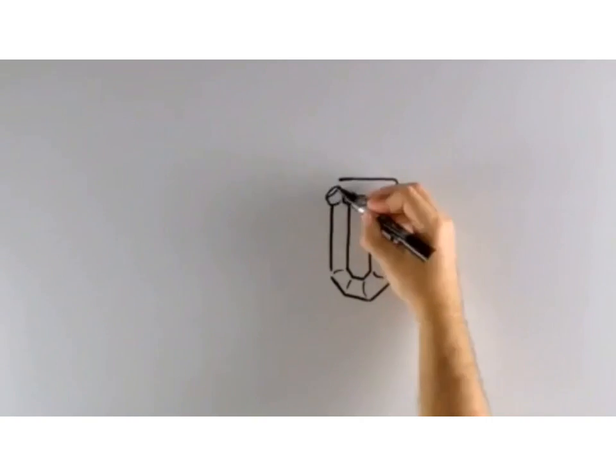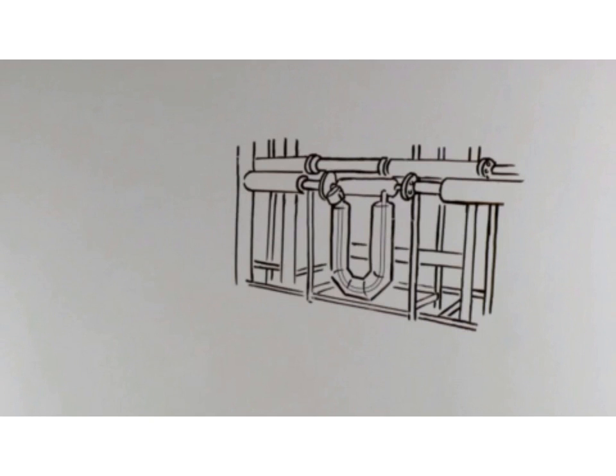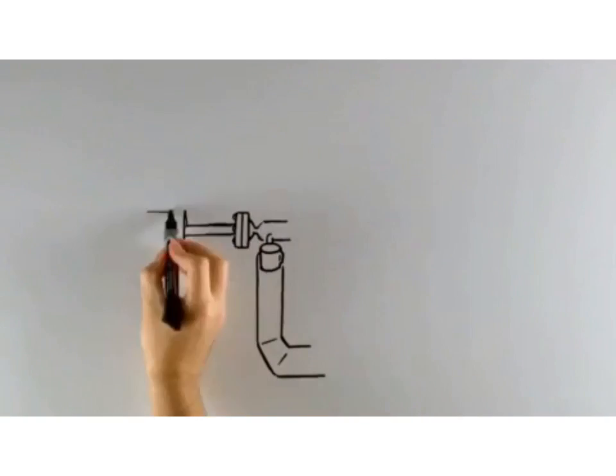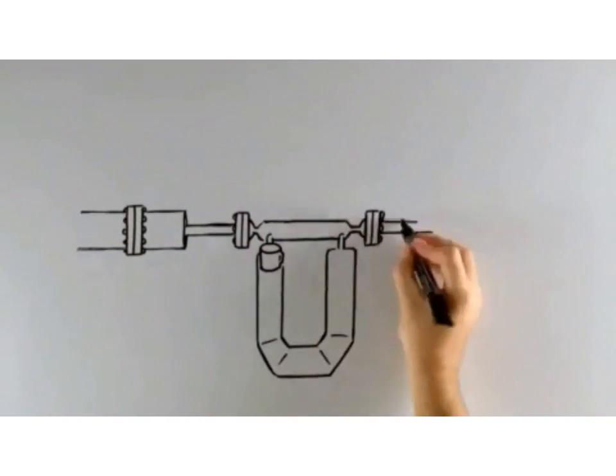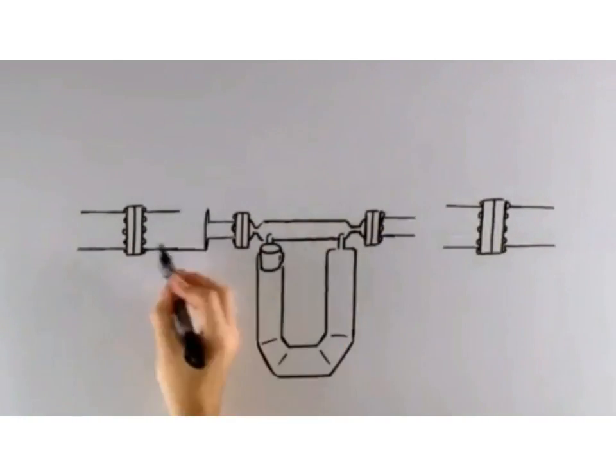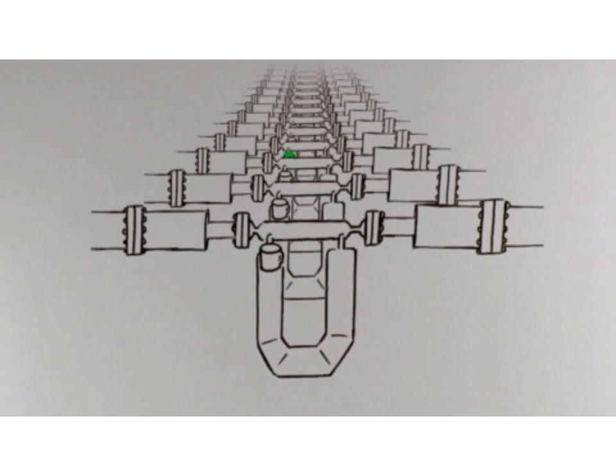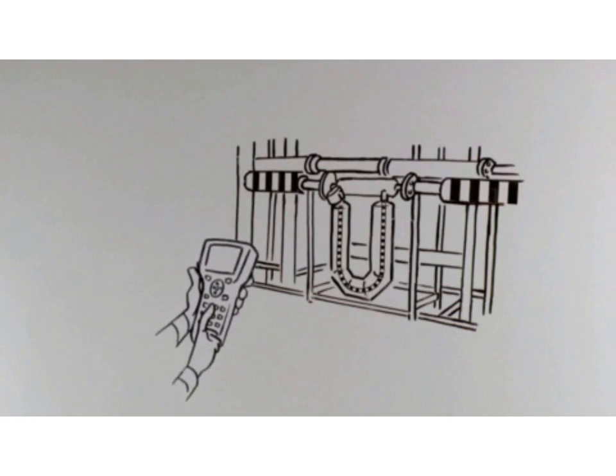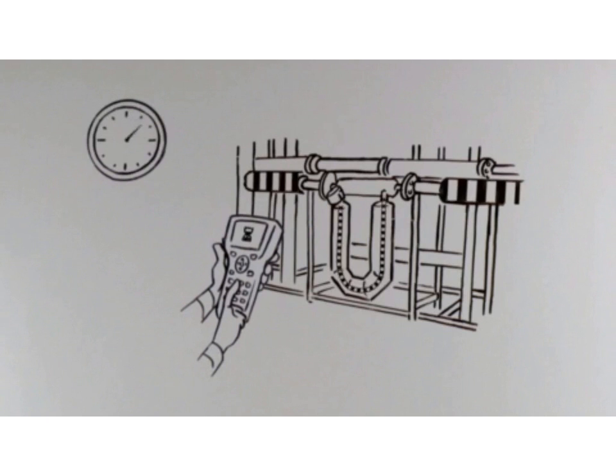SMV is the only in-situ, on-demand diagnostic system that tests the entire meter, verifying meter health, flow tube integrity, and electronics, all without having to interrupt the process. SMV ensures that the meter is operating as well as the day it left the factory. It's like having a virtual calibration stand built into every flow meter in your system. With SMV, Tom can verify his meter in 90 seconds or less.